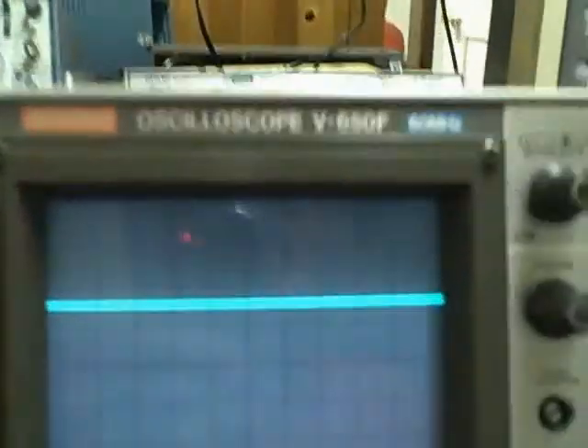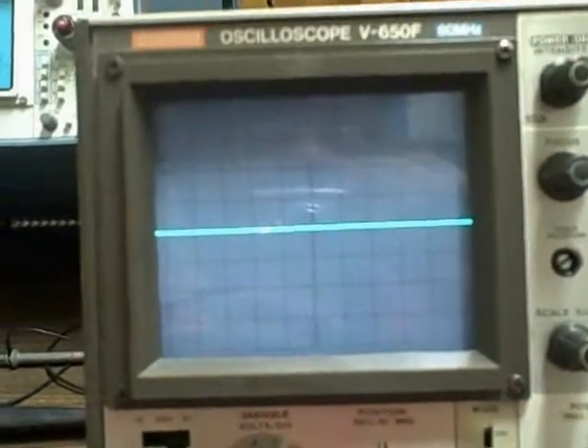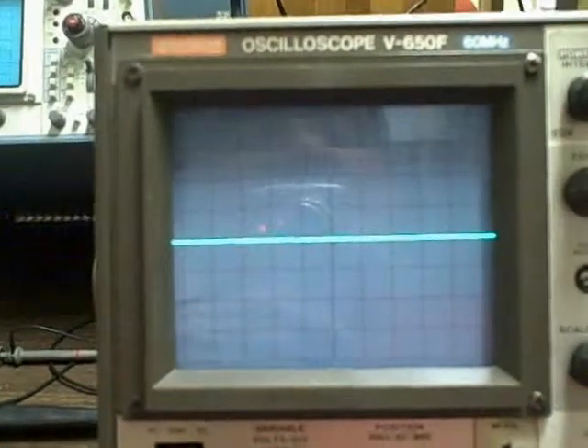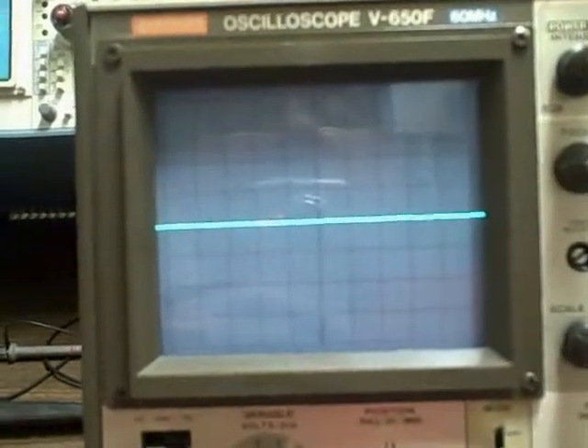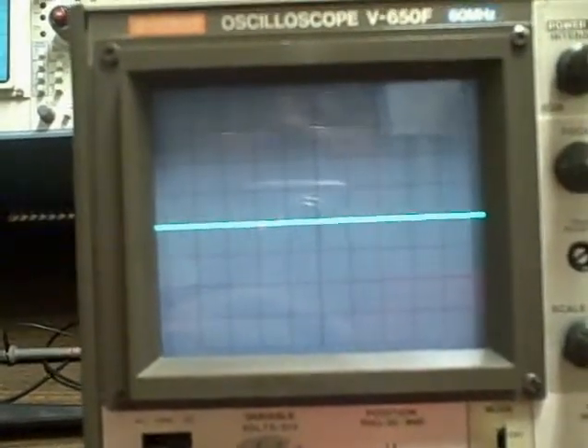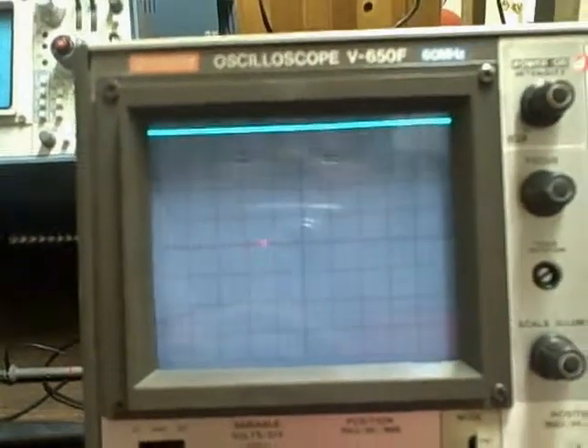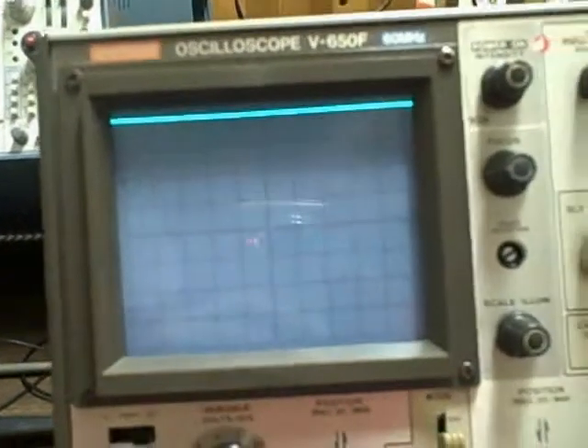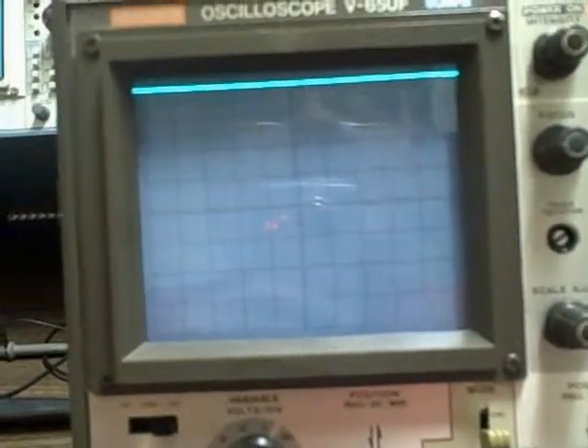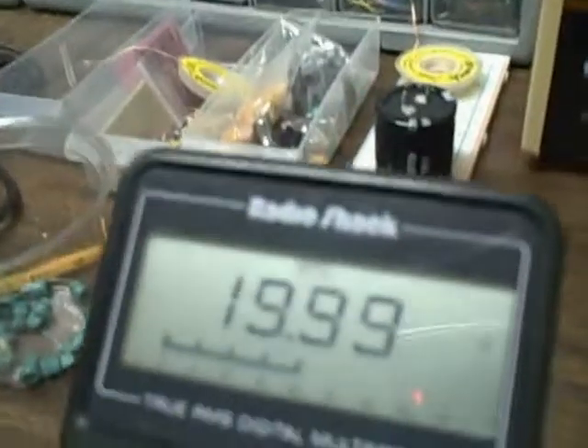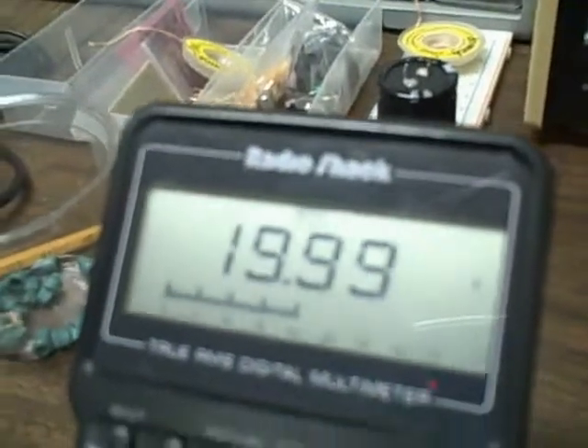And then finally we go to 5 volts. Okay, we're at 5 volts per division and we have just zeroed. Let's go ahead and bring her on and we've adjusted for full scale. We've achieved full scale, so that's 5 times 4 is 20 volts, and we are running 19.99 volts.